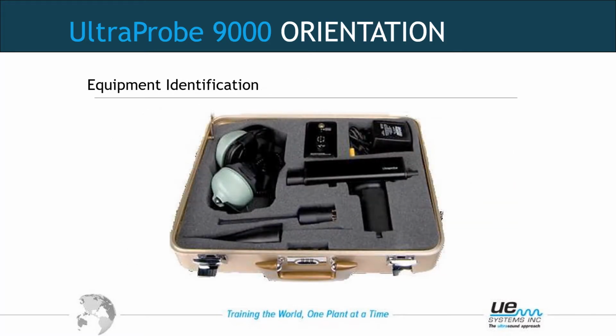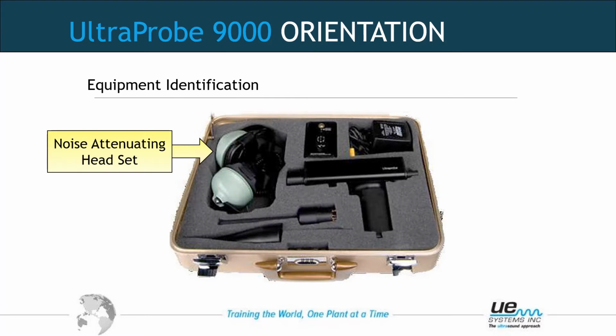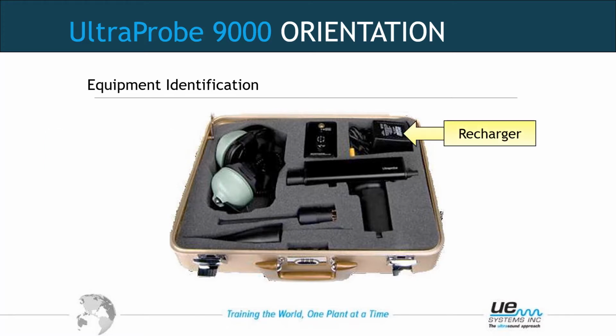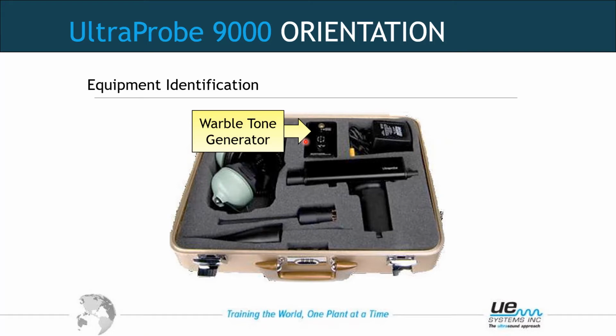What comes in the case? The Ultraprobe 9000 pistol grip inspection unit. The scanning module, which is used for airborne inspection. It is usually attached to the unit when shipped. Noise attenuating headset meets OSHA's regulations for single hearing protection. Recharger. The recharger will charge the pistol grip unit as well as the warble tone generator. The warble tone generator emits a false ultrasonic sound that can be used for sensitivity validation or field calibration check. You cannot calibrate this unit in the field, but you can check it.